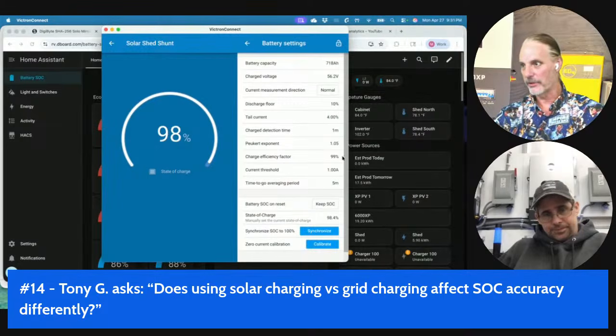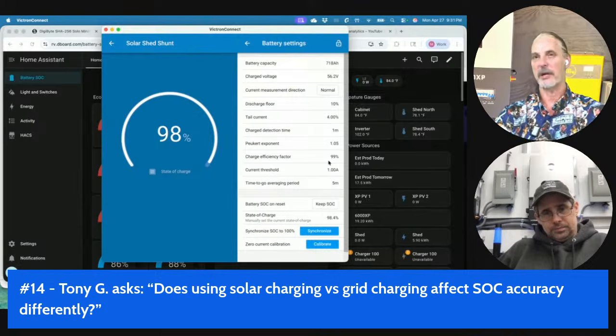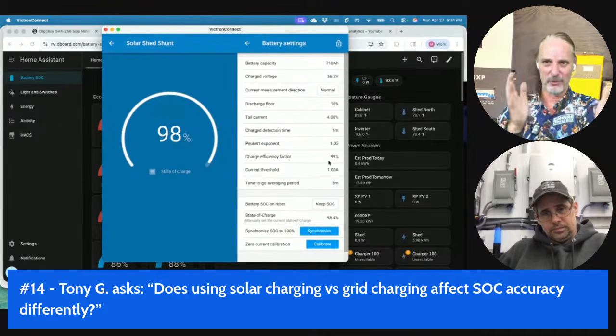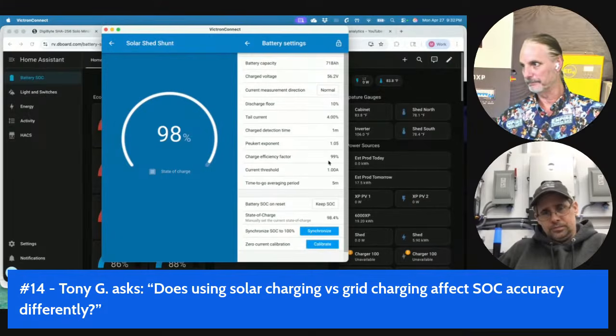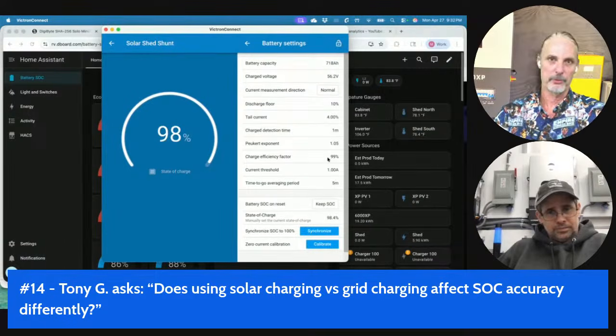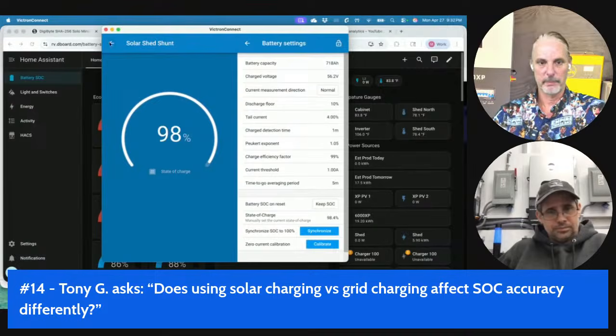But that's what all of this is about here with the Victron devices. It used to be very important that your lithium iron phosphate or your AGM or your lead acid battery had those settings correct, because it had a huge impact. Nowadays, as long as you stay within their region, I usually stay, especially if I'm just doing a grid charge, unless it's a battery test for the purposes of testing it, I won't usually do more than 0.2 or 0.3 C, which is 20 or 30% of its rated capacity, for those who don't know.